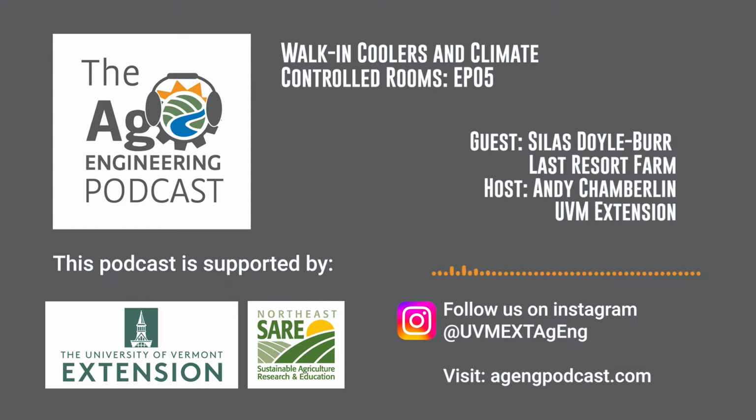What's tended to happen for us is that getting the set bandwidth for the commercial unit has been tough, to get it to be a consistent temperature. We've gradually dialed that in, but that's something where it's kind of hard to work on yourself. So if you're looking to do everything yourself, a CoolBot controlled unit is the way to go. But again, removing field heat and getting a consistent temperature as close to 32 as possible in the dead of summer, you really have to have a commercial unit.